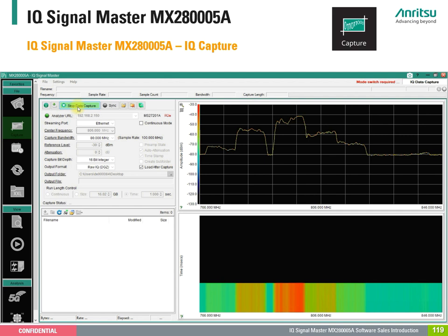Because you have initiated the capture, you can immediately switch over to replay the recorded signal. You can influence the time resolution of the replay and the replay speed. A marker functionality with a maximum of two markers allows for doing some frequency-related measurements. This is easy, right?